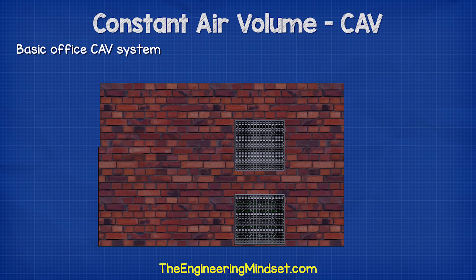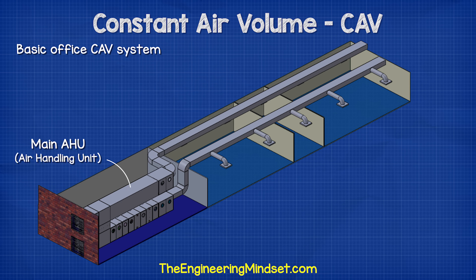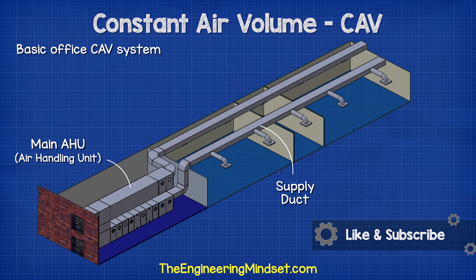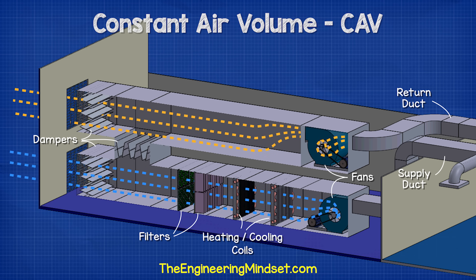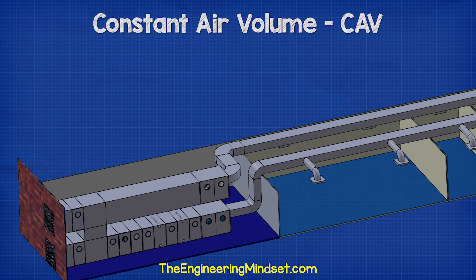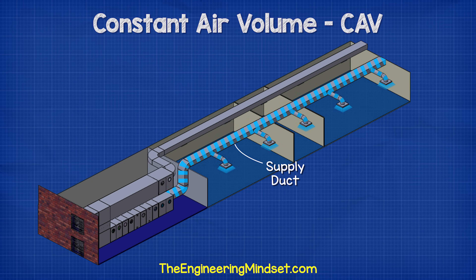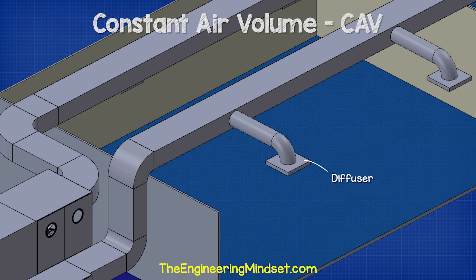Here we have a simple model of a CAV system for a small office. First of all, we have the main air handling unit which is located in the mechanical plant room. From this, we have the main supply duct. The fresh ambient outdoor air is sucked into the air handling unit, it is filtered and then heated up or cooled down within the AHU, and then a fan pushes this out down the ductwork to be distributed throughout the building. Coming off of the main supply duct are a number of branches, and each branch has a diffuser at the end.